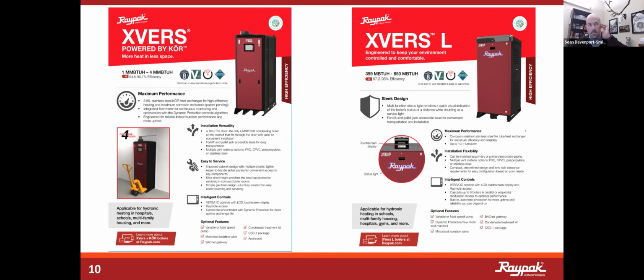Yeah, I was thinking, being involved with a lot of boiler projects, there's a lot of troubleshooting, and a lot of times it does come down to flow. Most other boilers, including this boiler, also come with a flow switch that only gives you so much information. That just tells you that you have enough flow to meet that switch. It doesn't tell you the exact flow through it.